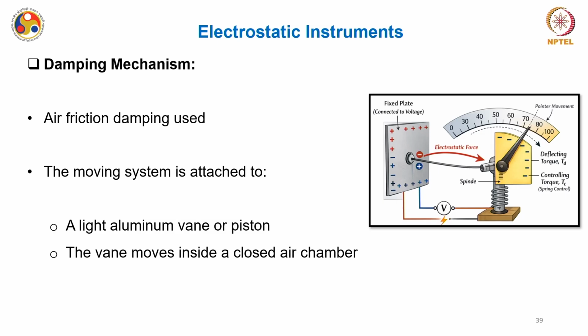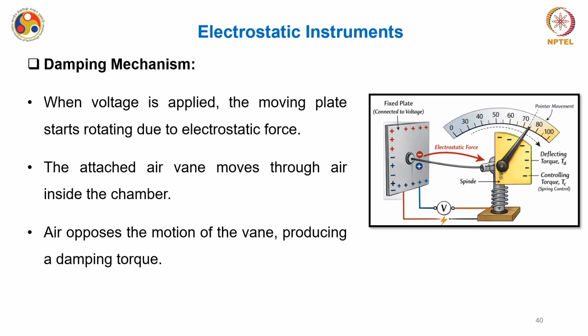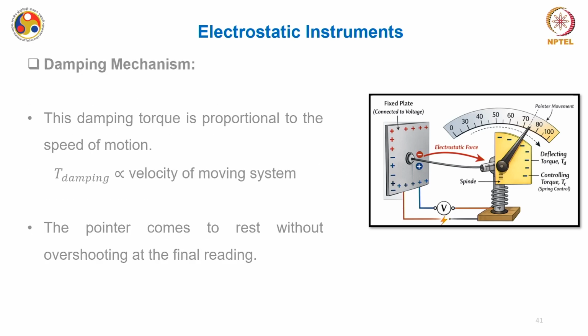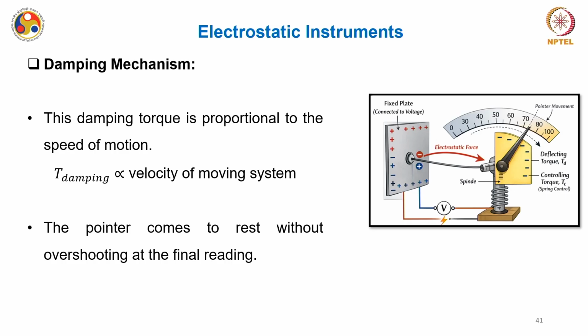The damping in the electrostatic instruments is provided by air friction. The moving system is basically attached to a light aluminum vane or piston, as we have seen in other instruments where air friction damping was used. The vane moves inside a closed air chamber similar to the one we have seen earlier. When voltage is applied, the moving plate starts rotating due to the electrostatic force, and the attached air vane moves through the air inside the chamber. This air provides an opposing force to the motion of the vane, which produces a damping torque. This damping torque is proportional to the speed of motion. So if you increase the velocity of the moving system, the damping torque will also increase and will try to minimize any oscillation at the end point. The pointer comes to rest without overshooting at the final reading, as is the case with most air damping systems.